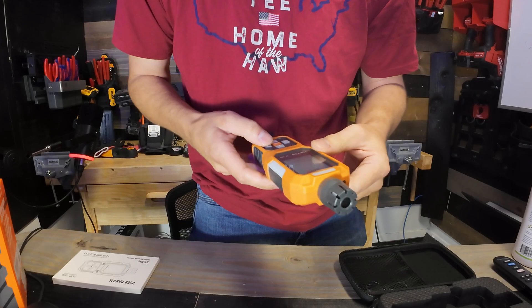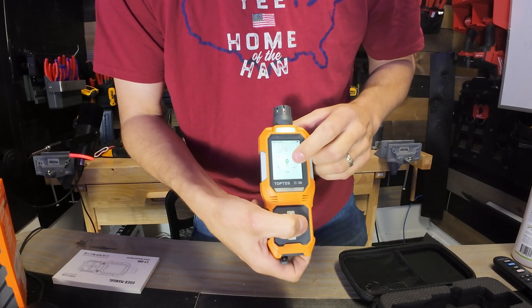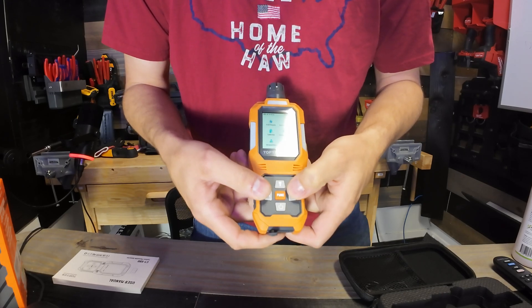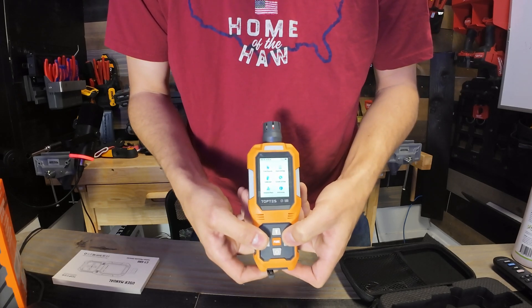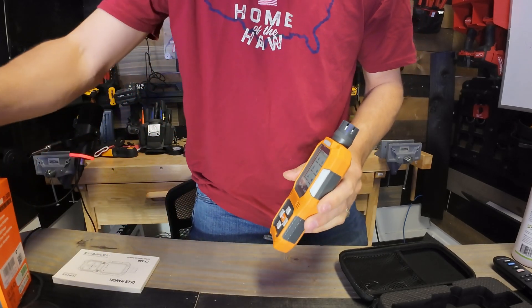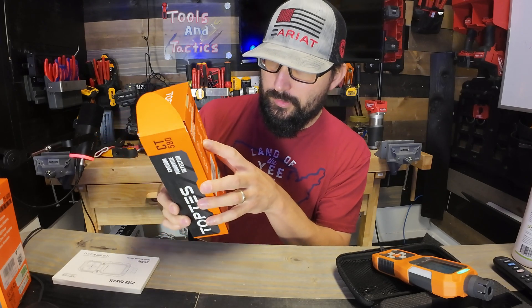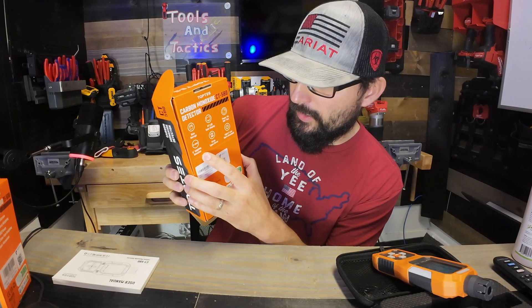There's a flashlight built in up here, which is very useful if you're in the dark. There are multiple functions — different ranges, a graph view versus another way of showing data. The power button navigates back. Menu options include alarm settings, event records, calibration, system settings, advanced menu, and information. Specs include data storage, a TFT LCD color display, power-on self-test, detection range of one to one thousand parts per million, three alarm types, and high and low alarm thresholds.